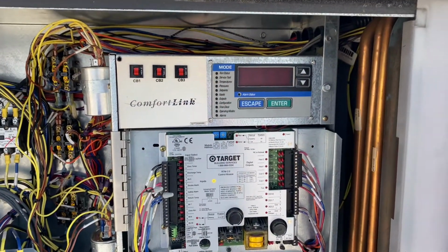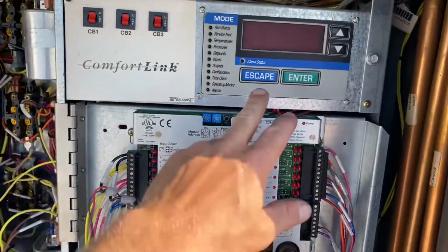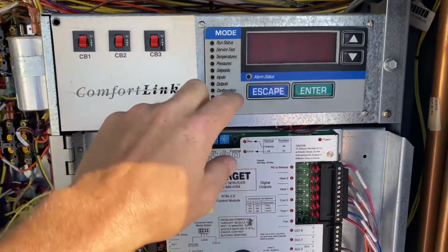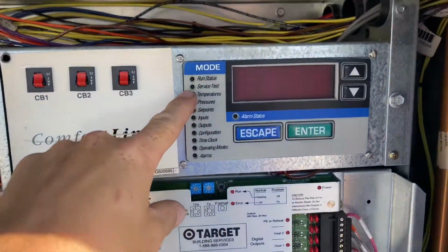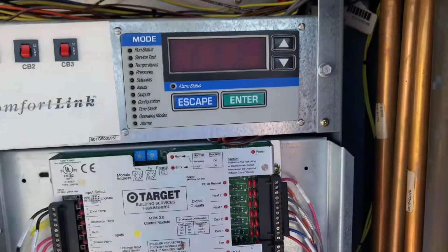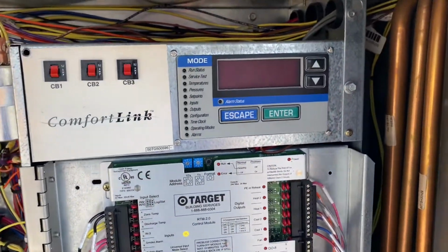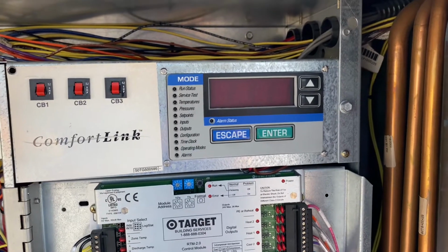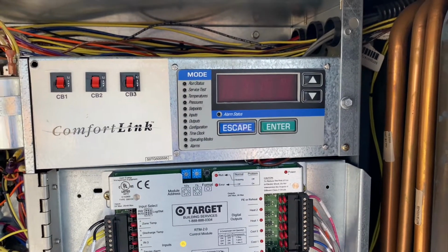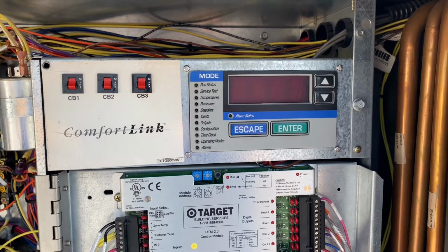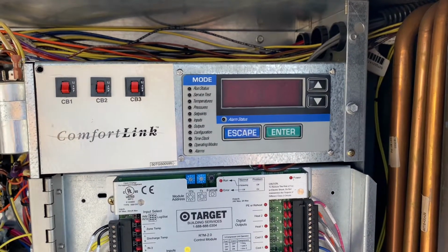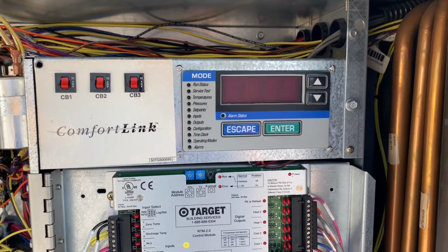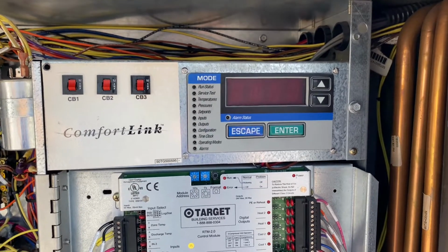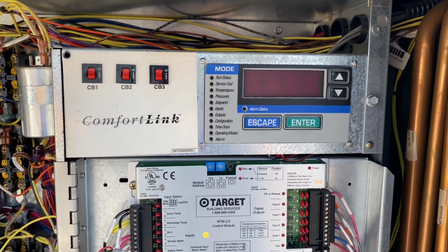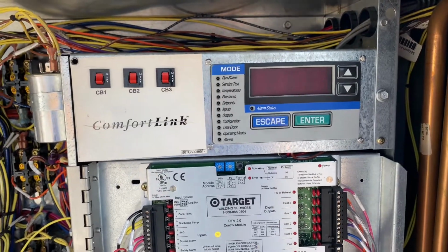I quickly got it into test mode, which just requires hitting escape from the menu, cycling down once to service test, and hitting enter. Sometimes you have to enter a password. From all I've seen, if it does ask for a password, it's just 1111. And got it in test mode, cycled down to outdoor fans, and went to test fan number 1, and pop, blew the fuse.